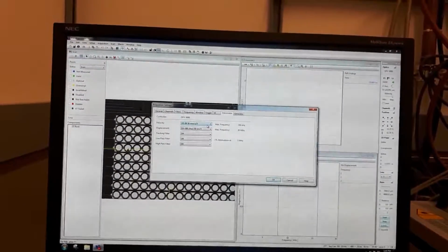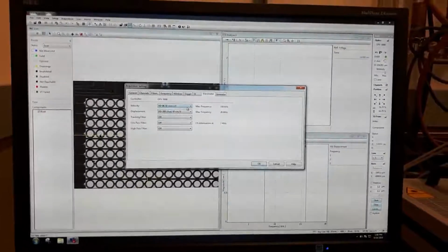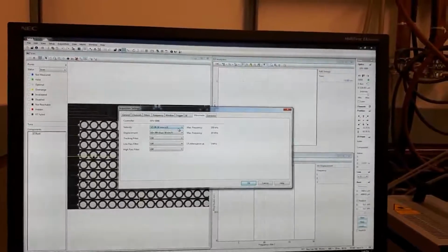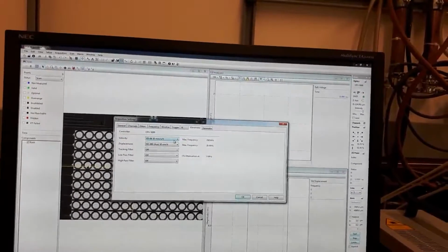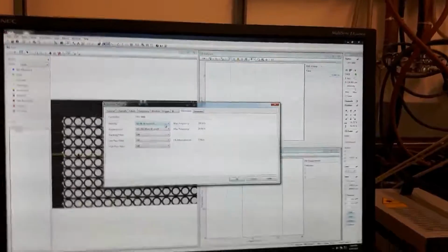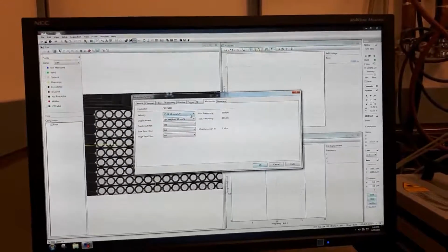So, rule of thumb, select the decoder that falls within the range of your measurement. If you want to measure something that vibrates at 80 kilohertz, then select the decoder that has a maximum frequency of 100 kilohertz. This way you'll have almost full resolution of your decoder, the highest bandwidth. Otherwise, if you use a higher decoder, you can still get measurements, but you'll be wasting a lot of bandwidth of the decoder.